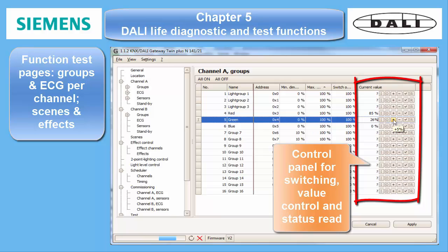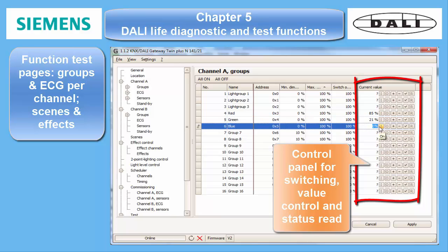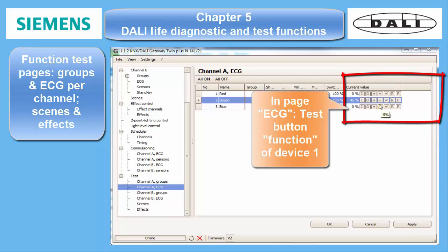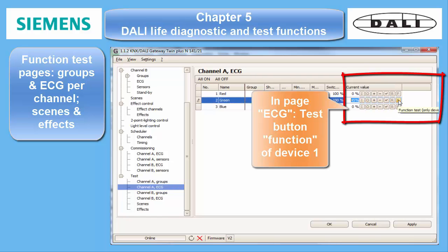The test panel allows all possible controls: on, off, plus, minus, steps of 5%, direct control by sending a value that you have inserted in the current value column, and reading out the current status of a group or of an ECG. In the panel for ECG test, an additional function test button is available for device type 1, emergency lighting ballasts.